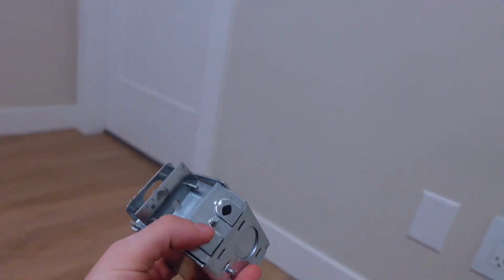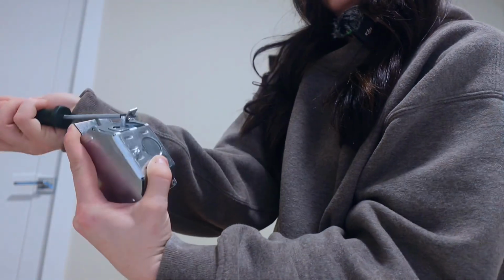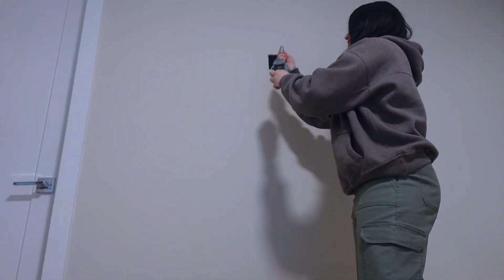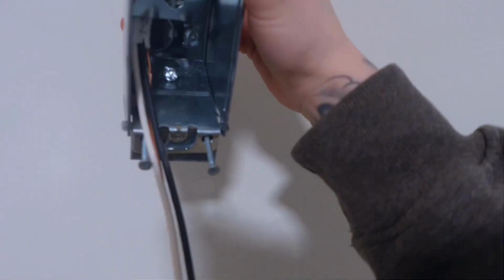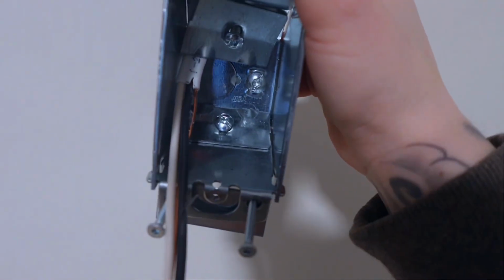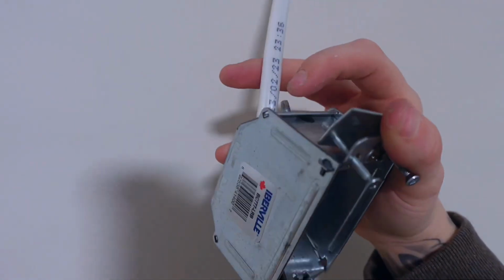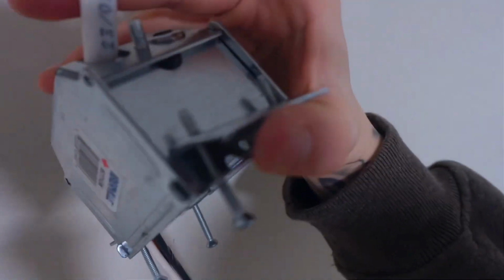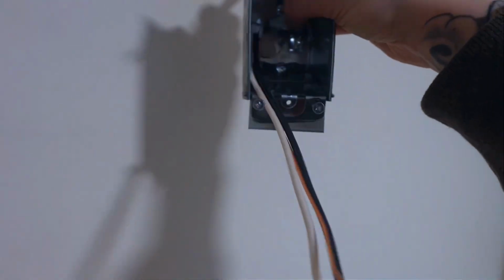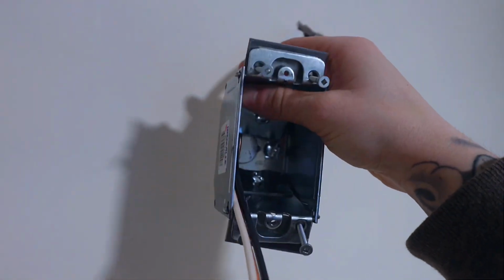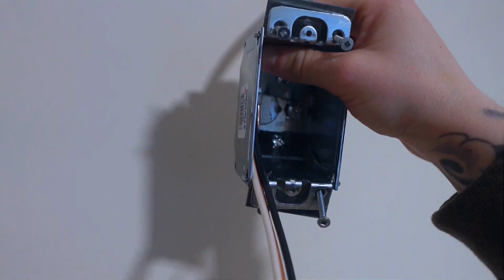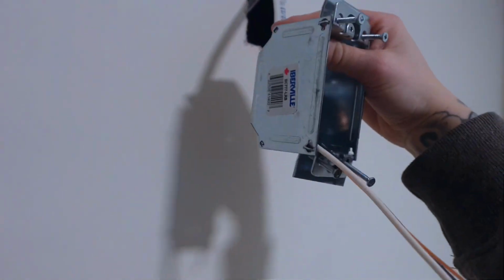So we stripped this wire the same way that we stripped the other one. Now we are going to break off one of these tabs in the back here. Push your wire through the hole. It's important that some of the insulation comes through the box. You don't want any of the wires sticking outside of the box. But before we go ahead and screw this bracket down that pinches the wire into the box and secures it, we're gonna wanna get the box into the wall.